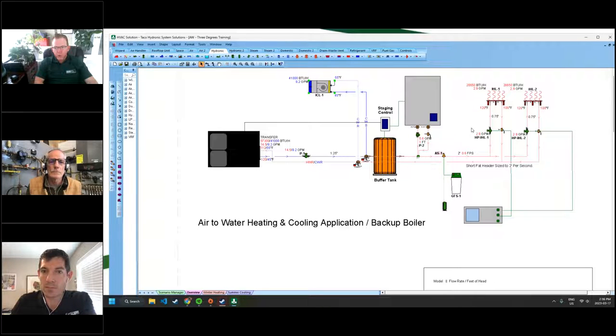So what happens in this control logic is that the staging control, which is basically just monitoring this tank from a heating standpoint, if these loads call and if this tank doesn't have usable heat, and what I mean by that is if we designed these radiant floor systems to need 120 degree water, this control can see the buffer tank is only 100 degrees. It'll bring on the backup boiler, whether it's electric or gas or whatever it is. And instead of lifting the water from cold, it's lifting it from 100 degrees to 120 degrees.